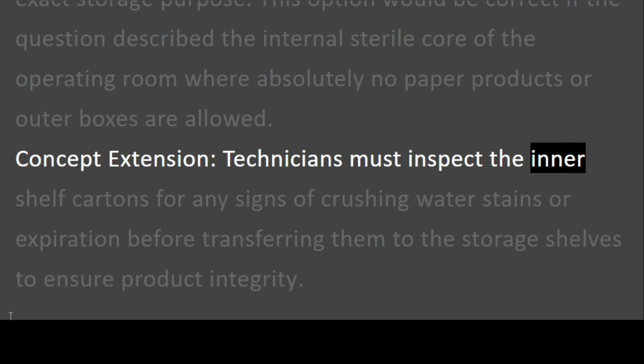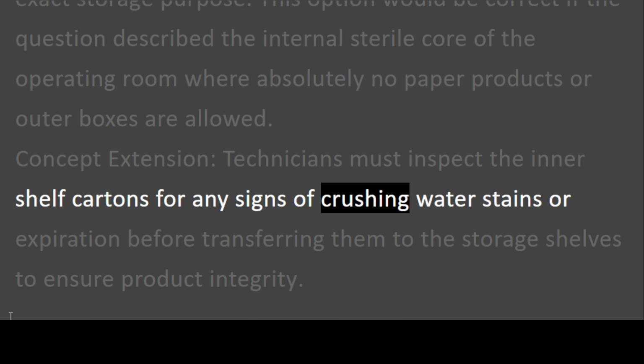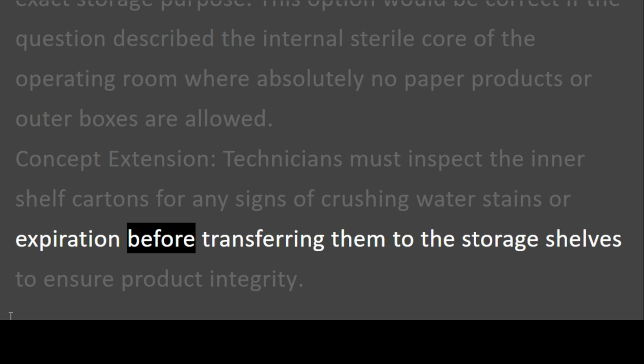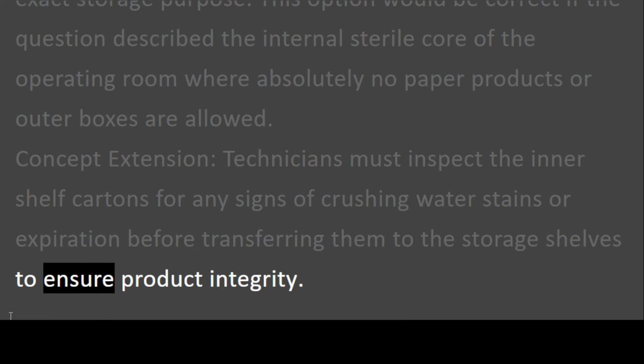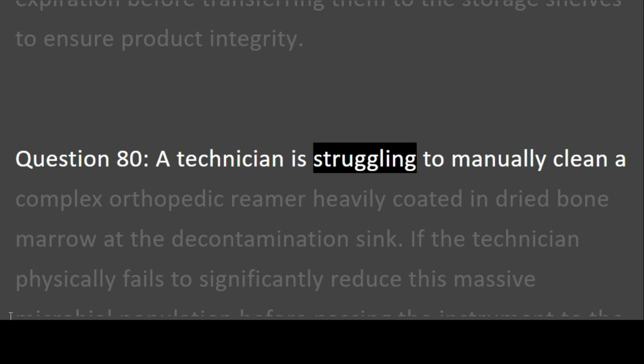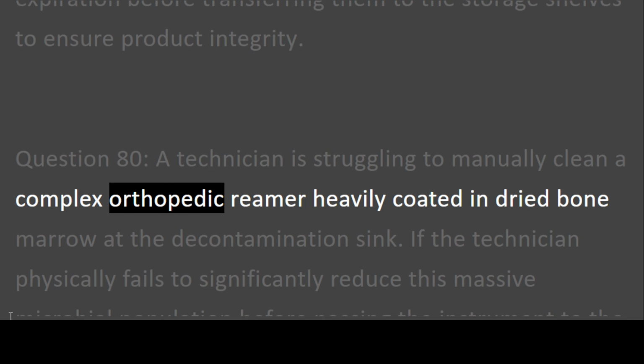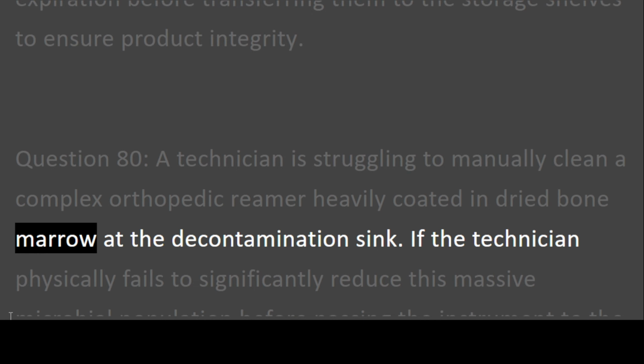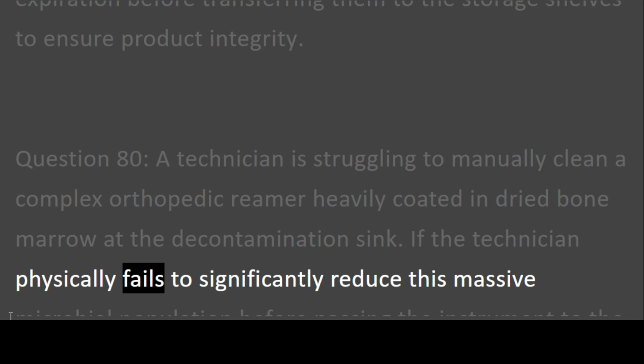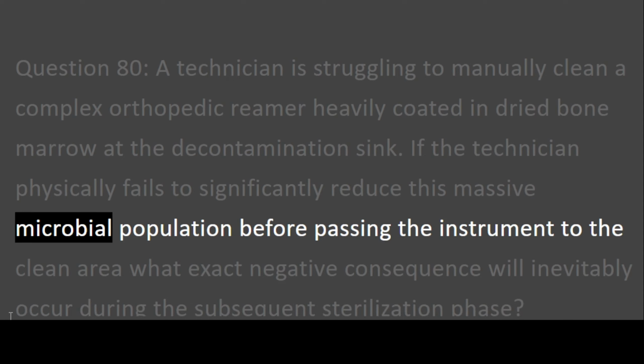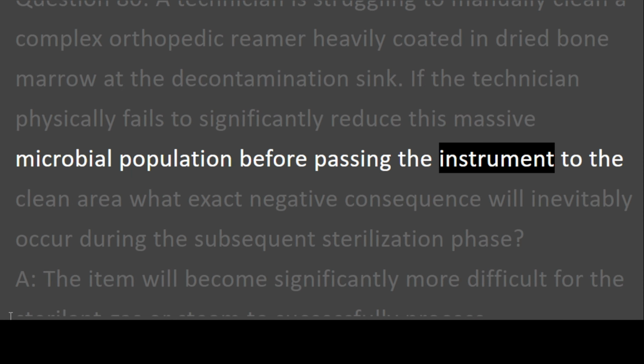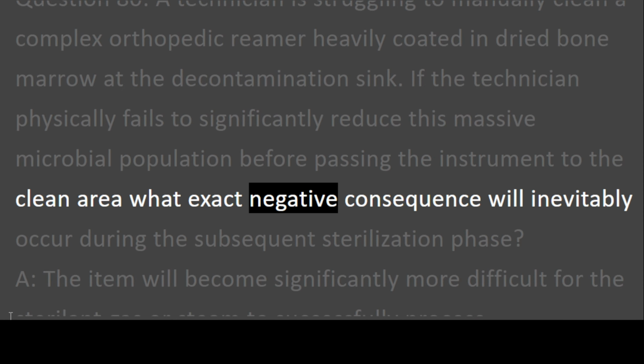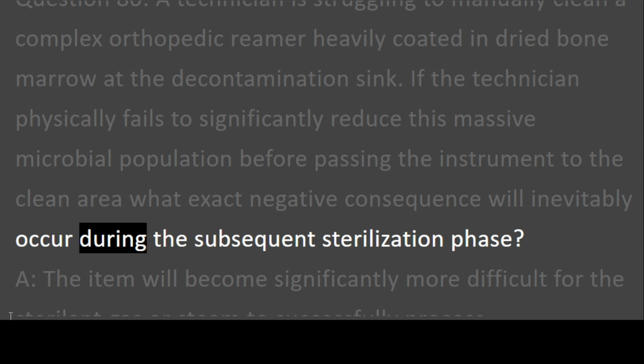Technicians must inspect the inner shelf cartons for any signs of crushing, water stains, or expiration before transferring them to the storage shelves to ensure product integrity. Question 80. A technician is struggling to manually clean a complex orthopedic reamer heavily coated in dried bone marrow at the decontamination sink. If the technician physically fails to significantly reduce this massive microbial population before passing the instrument to the clean area, what exact negative consequence will inevitably occur during the subsequent sterilization phase?